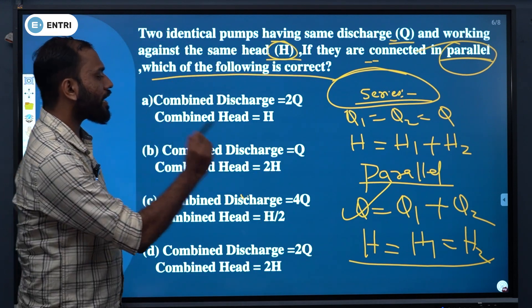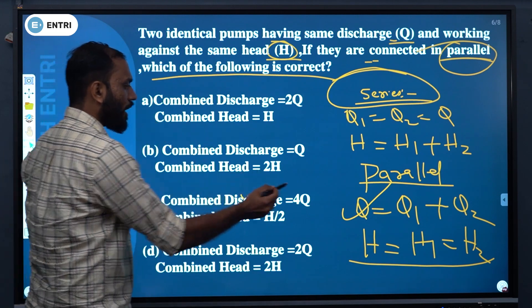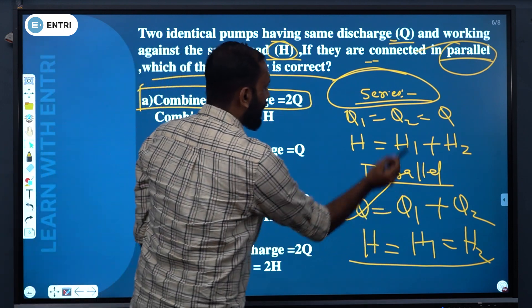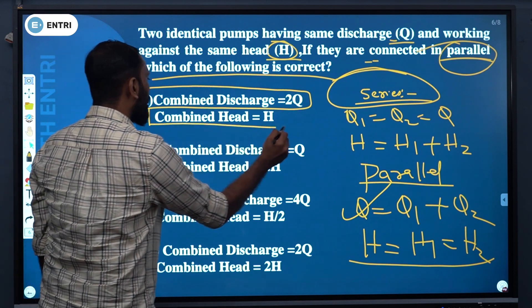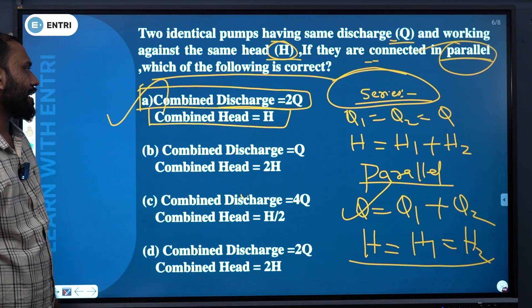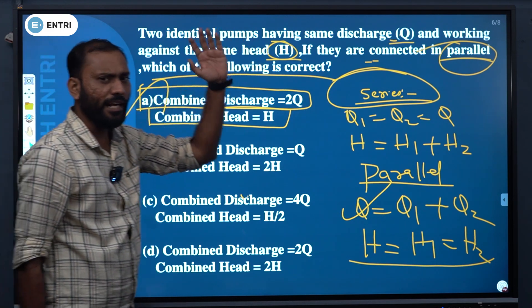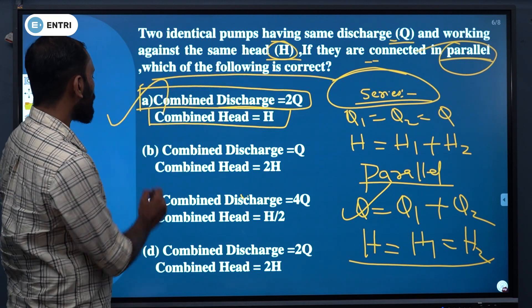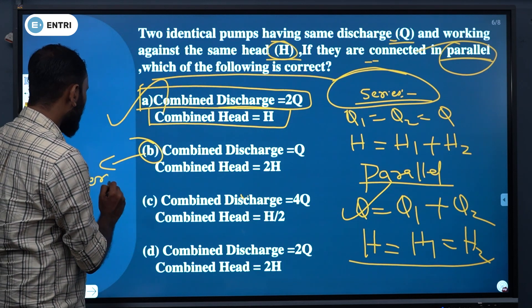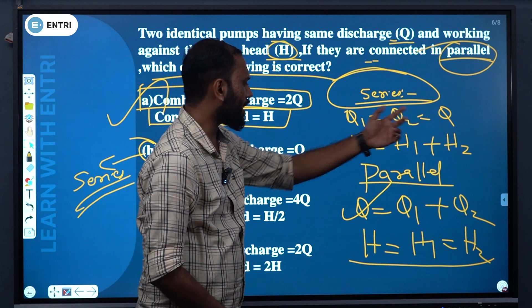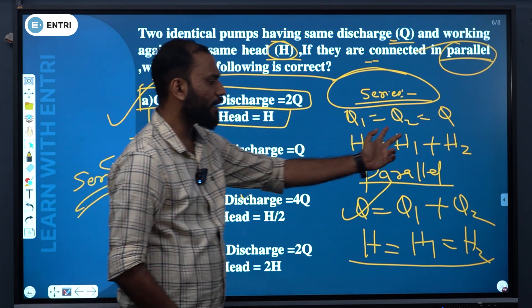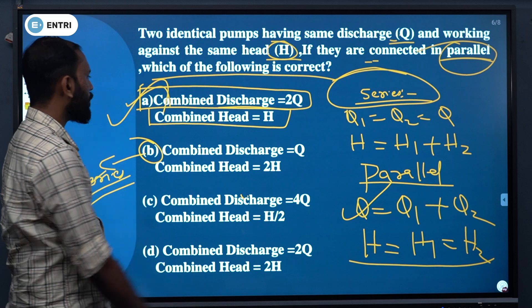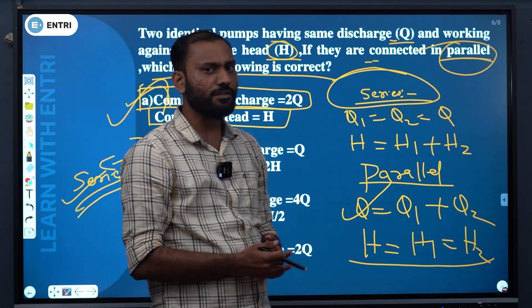For a parallel connection, the head remains the same. So, option A is correct. In a parallel connection, the discharge doubles while the head stays the same. In a series connection, the discharge stays the same and the head doubles — that would be option B. So for parallel, option A is correct. Series connection and parallel connection in multi-stage pumps is very important.